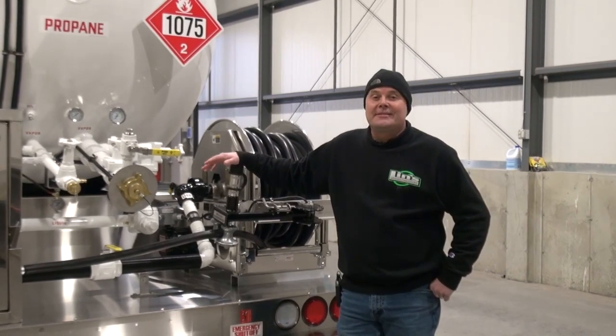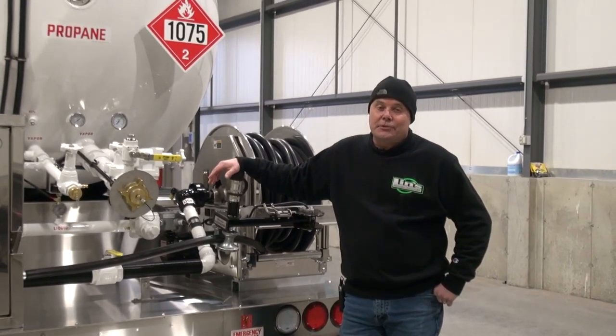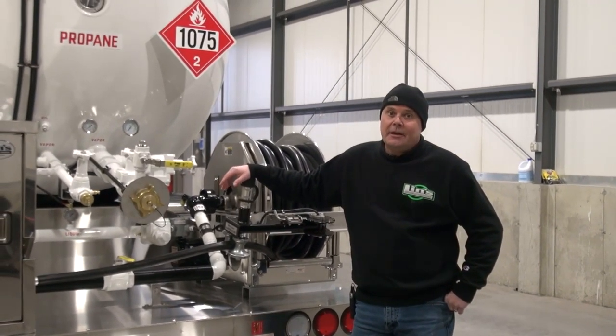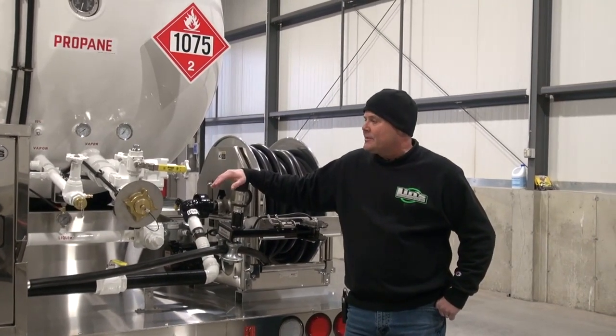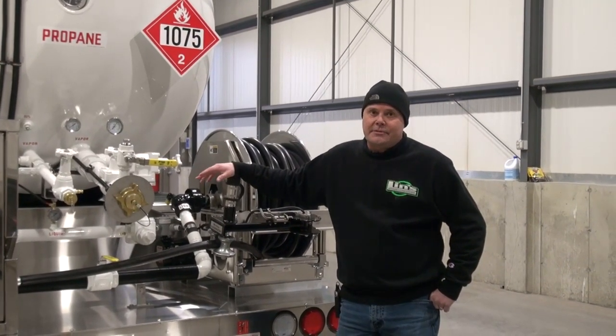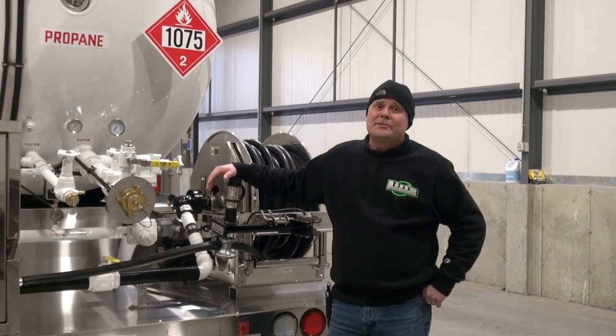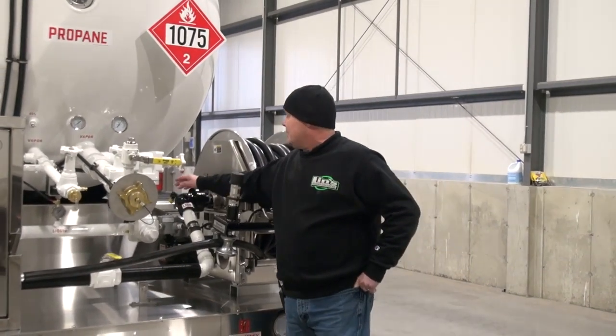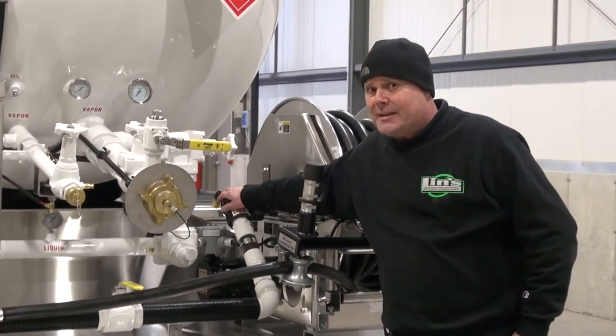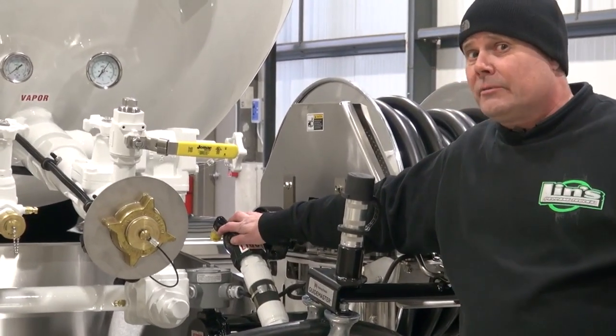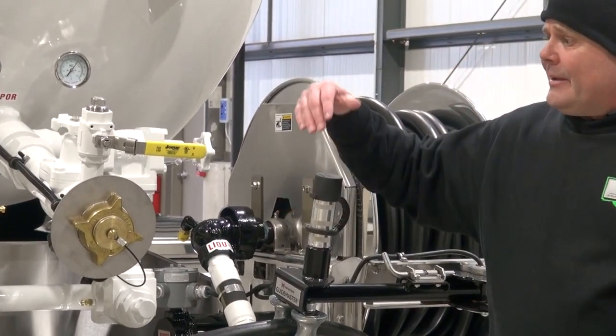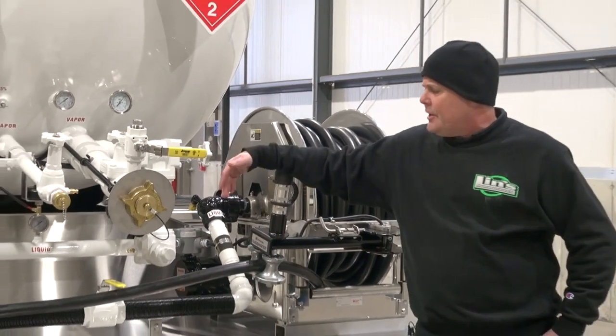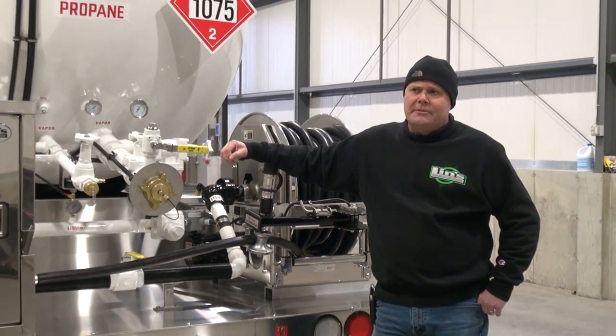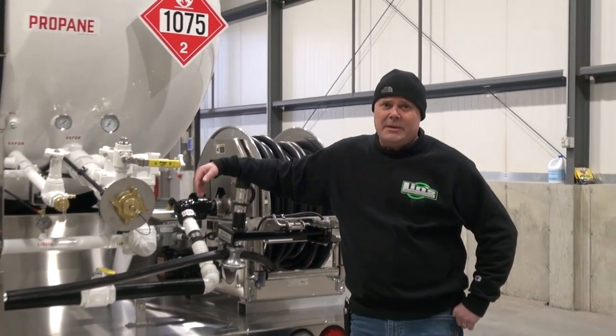We recommend isolating the stable flow heat exchanger from June 1st through September 1st. The reason for that is that in the summer months, you're operating at higher pressures. And though it's not common, it is possible that you could have a brief release from the 1/4 inch 450 PSI relief valve on the full circle swivel. Remember, when the temperatures get into the 90s, you could have pressure in your piping upwards of 165, 175 PSI.